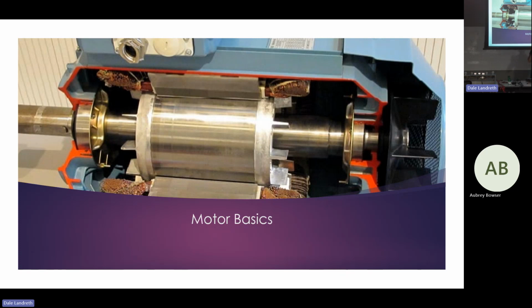Has anyone ever tried to meg a motor with power factor capacitors? What does it do? It reads shorted. Reads short, reads bad, right? You're like, dad gum, I got a freaking motor bad. But it's not. You got to disconnect those things again. Let me tell you how embarrassing that is when you mess that up. When you do it the first time, you already tell the customer, then you call Faber - it ain't freaking shorted, it's got power factor capacitors. I don't know, what's that? Exactly. So those are things you got to watch out for.